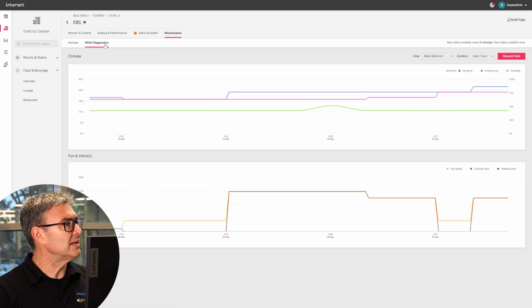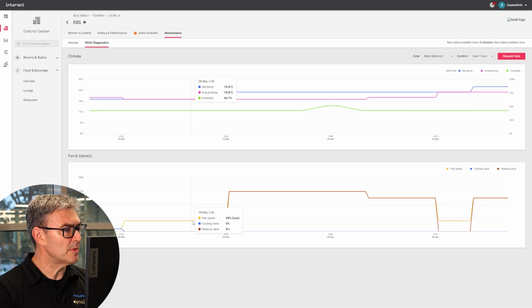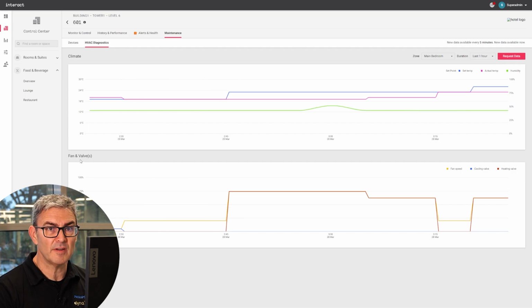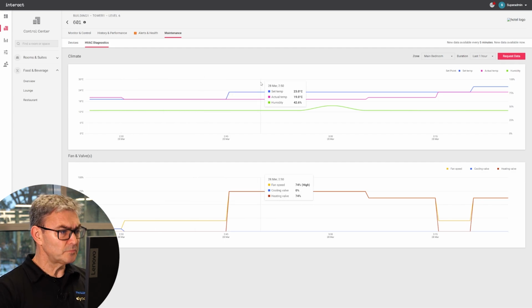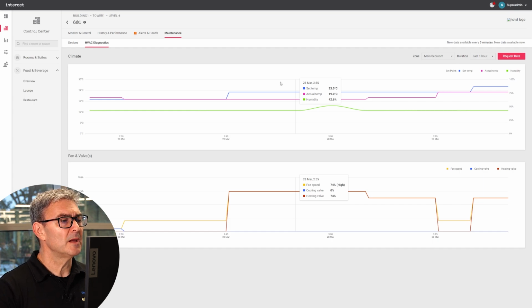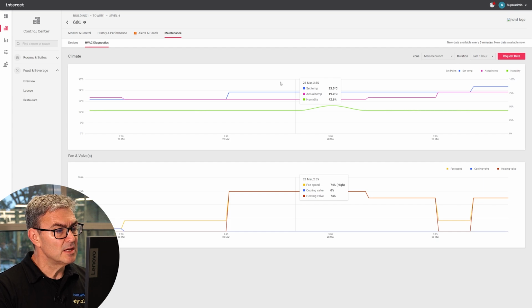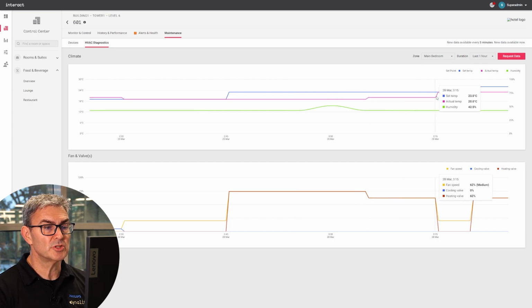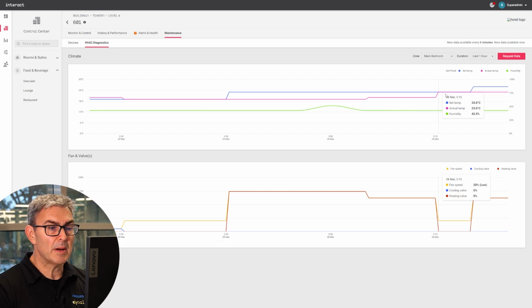So it's right here under Maintenance, HVAC Diagnostics, and I can see the climate information, which is the in-room, and then I can now see the fan and valve states. So, for example, if I look here, my actual temperature is 19, my set point is 23, so as expected, the heating valve is on 3/4 and the fan is on 3/4, it's driving the temperature up in the room. Once the room comes up to speed, I can see here I've got parity between actual temp and set temp, both valves are off and the fan speed has dropped.